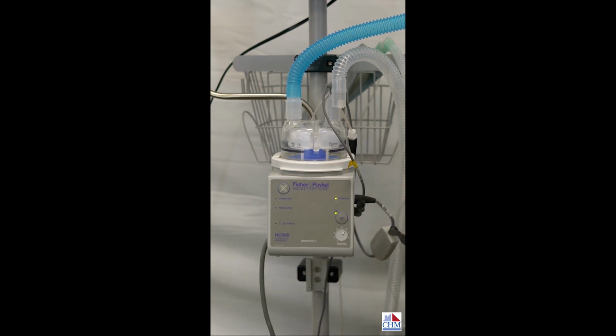The temperature alarm is probably the least common, least troublesome anyway. Temperature can come on if we lose water or run out of water in the chamber. Maybe we don't have the blower going with the trach humidity, or the Trilogy is not running at the time. We just forgot to turn the heated humidifier off. That'll cause a temperature alarm. Or if there's a real malfunction with the machine, it's designed to let us know it's not making temperature.